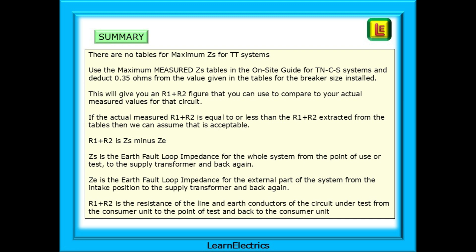R1 plus R2 is ZS minus ZE. ZS is the earth fault loop impedance for the whole system from the point of use or test to the supply transformer and back again. ZE is the earth fault loop impedance for the external part of the system from the intake position to the supply transformer and back again. R1 plus R2 is the resistance of the line and earth conductors of the circuit that is under test from the consumer unit to the point of test and back to the consumer unit.